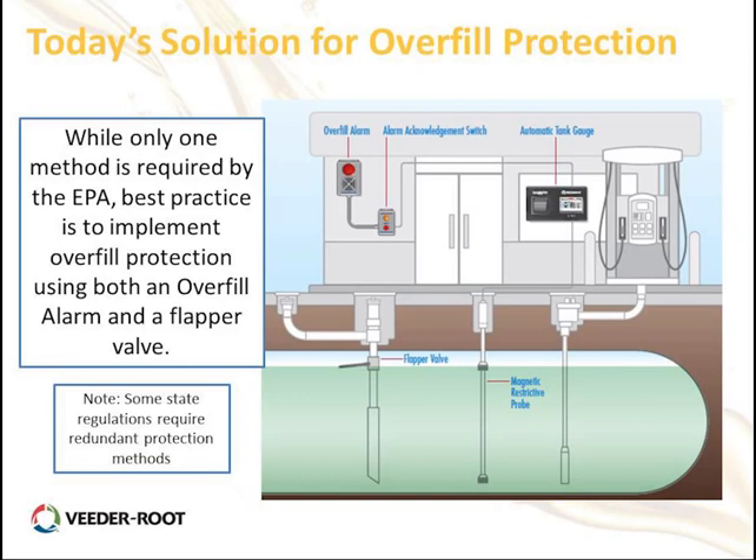You can use one method based on the regulation, but if you have an ATG already installed at your site — like the Veeder-Root — you have the capability to produce this external alarm and light indicator. Some regulatory bodies require redundant protection methods such as the flapper valve and the ATG together, so verify that with your local agency.